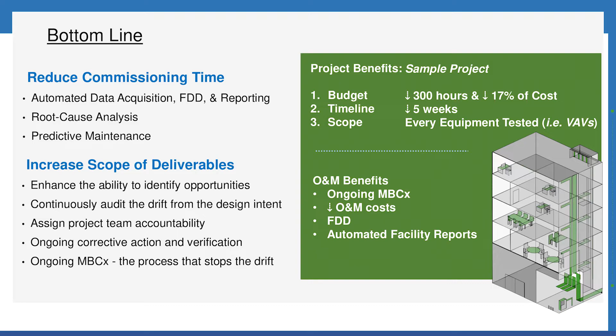One of the biggest struggles in this field is having to go to either a controls contractor or the BAS directly, download the data, upload it to your analytics server, and then deal with munging the data and so on—it's very time consuming. Having an EMIS automates the data acquisition step, because you're talking to the BAS controllers directly and pulling that data straight from them.